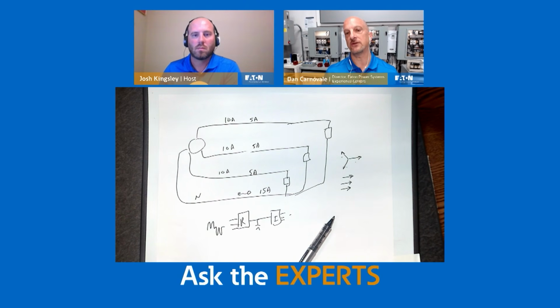So again, I'll get back to you on some of the details of that, but where I've seen this in larger industrials is the influence of those currents coming through, not the conductors themselves, because there are no conductors in your situation, but the capacitance to ground. They can follow that capacitive path, especially the higher frequencies. And that's why the EMI filter was likely recommended. And if it took care of the problem, that would make sense, because you're actually putting a conductor in parallel with that capacitance to ground. It's a very complicated situation, but I'll definitely reach out to you and talk through the details of the answers to that.